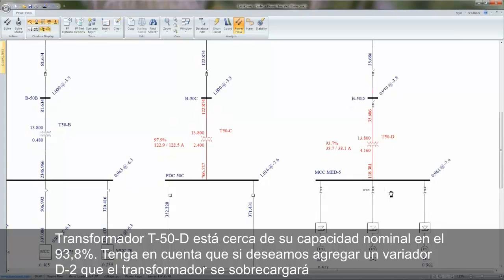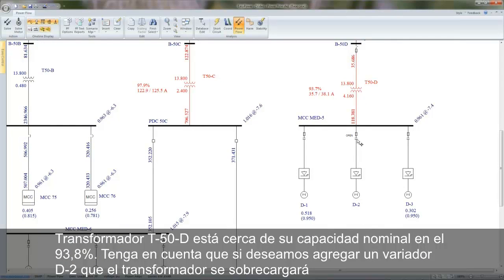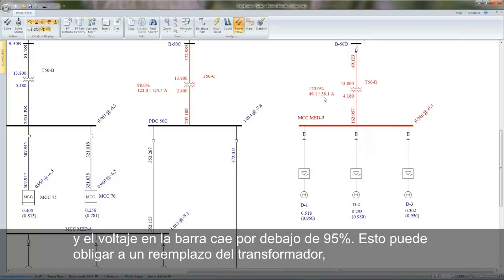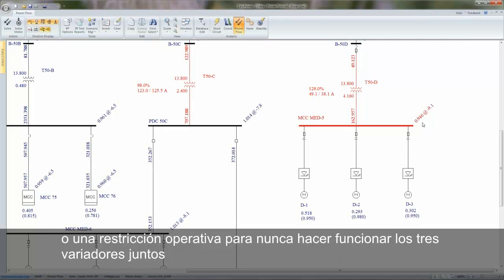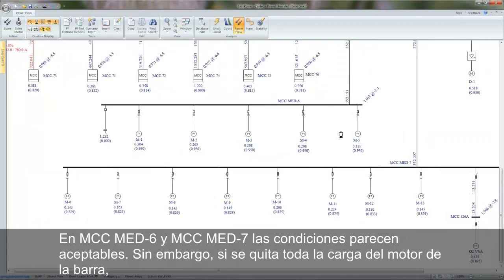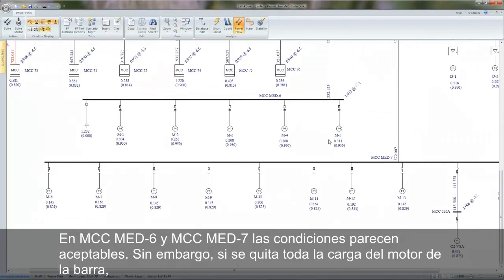Note that if we desire to add drive D2, however, the transformer becomes overloaded and the voltage on the bus drops below 95%. This may force a transformer replacement or an operational constraint to never run all three drives together. On MCC medium 6 and MCC medium 7, conditions appear acceptable.